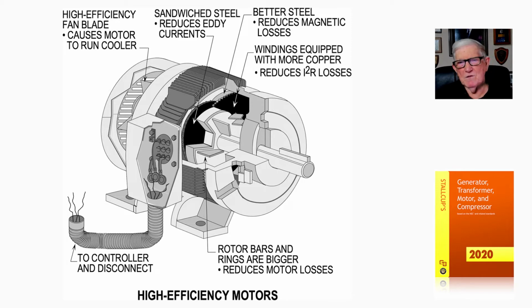The only thing about these motors is they have a very high inrush current, because you're building with the steel and everything better, and it reduces resistance and impedance of the motor, so it really draws a lot more inrush current, just like a transformer. You know, if you had a transformer that put out 1,000 amps and you had a 2% impedance on the transformer, well, 2% into say 1,000 amps, 50,000 amps. And say that you said, no, I'm going to raise that impedance to 4%, then 4% into 1,000, it'd only be 25,000 amps of short circuit current.